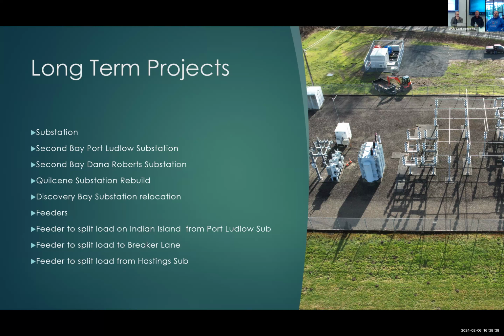Completed by mid-April, we are looking to put in a second bay in Dana Roberts substation. Part of the reason we're doing the Dana Roberts substation prior to the Hastings substation is Dana Roberts was built for a second bay to begin with, which allows us to bring a transformer in without doing as much of the steel and bus work as we would if we added on to Hastings substation.